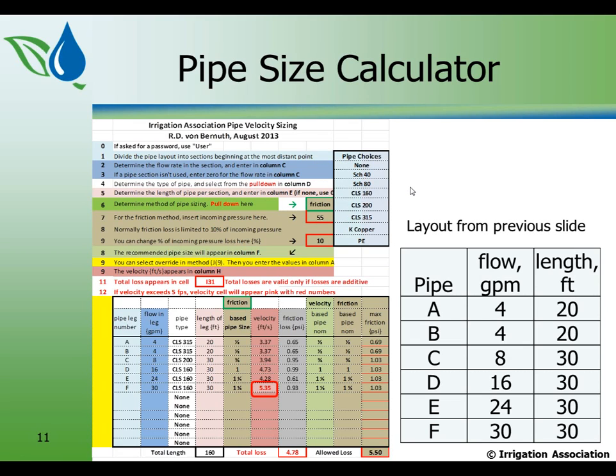Okay, Bob? Now, I want you to pay attention here to 2 numbers and sort of catalog those. We will see right here, and let me back up and that'll flash up again for you, that it shows 5.35 as the velocity in section F of this pipe right here. And it also shows that 0.93 is the friction loss in that section of pipe. So remember that or write it down, 5.35 and 0.93.